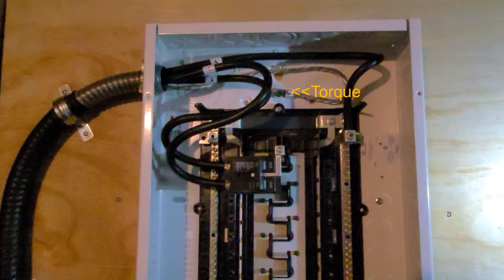A lot of the time the problem is a bad connection between the breaker and the cable. And then you can see here we have a stripped piece of insulation off here. That is required by the code. Because we are using the ACWU cable, we don't have a big connector here. So in order to get a good connection, we have to strip a little bit of insulation and put connectors here. But if you are using a Teck cable, use a Teck connector, that will be a different thing.